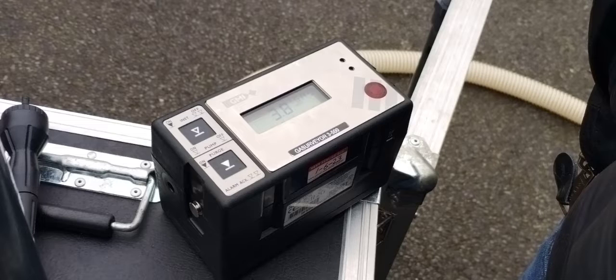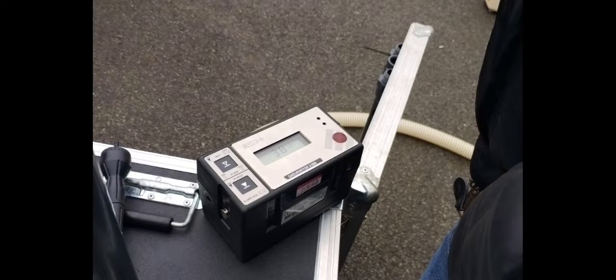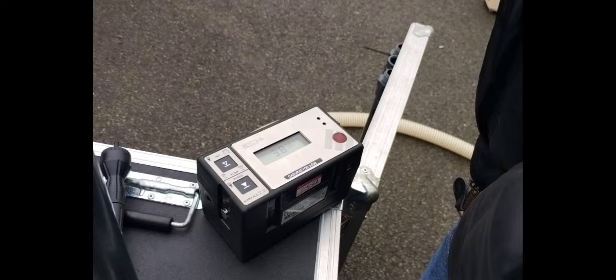When you're purging to air, you need to have 1.8% of gas in air for your purge to be safe on the air side when you want the installation to be full with air and gas out of the equation.